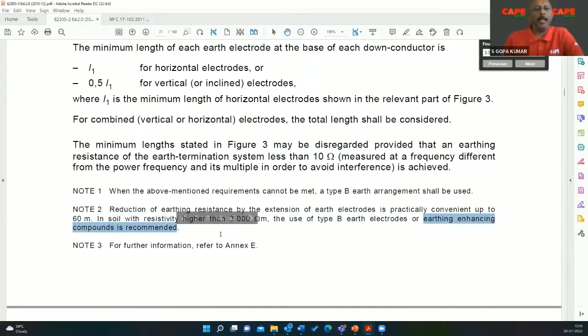Now practically in India, in most places we have soil resistivity of probably 100 ohm meter, 30 ohm meter, 50 ohm meter, 200 ohm meter. For that soil resistivity, of course, the earth enhancing compound is not necessary, and earth enhancing compound will only accelerate the corrosion.